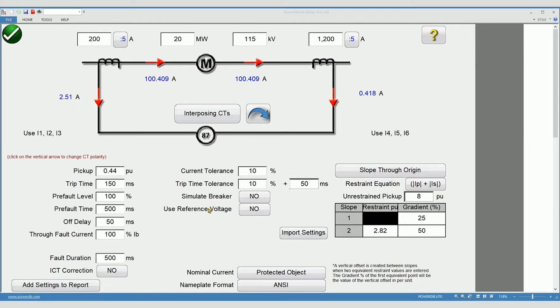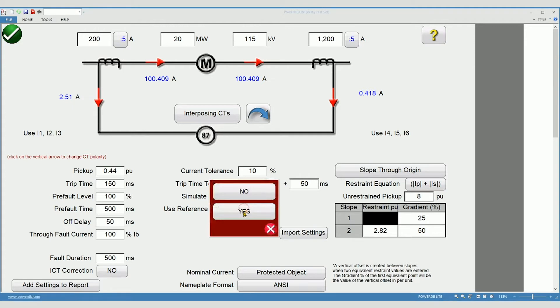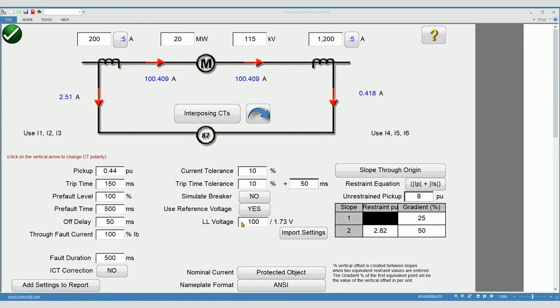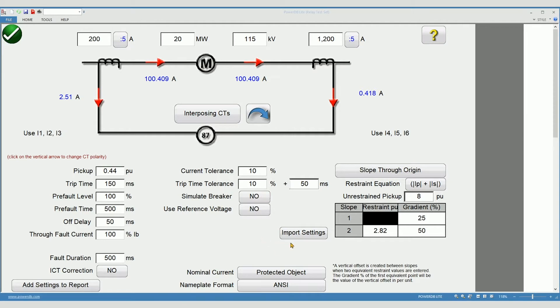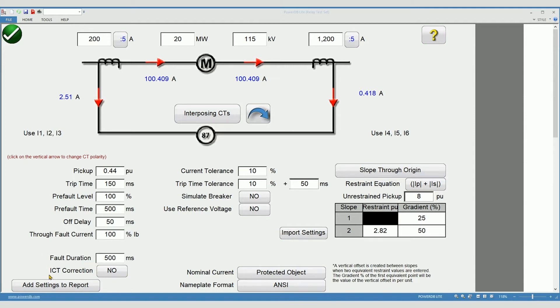If your relay needs voltage to enable differential protection, select yes and enable the voltage magnitude here. The import settings feature is still under development and cannot be shown today. Fault duration is the length of each fault pulse as the relay is tested. ICT correction is not used for generator and motor differential protection.